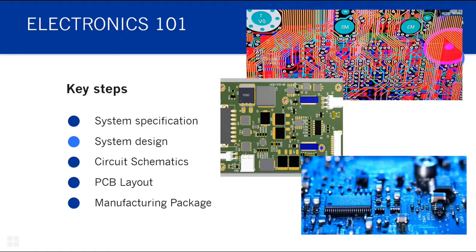Yeah, indeed. The circuit board will typically have a microcontroller on it that hosts the software, and that is what makes the device actually work. So I have been known to make disparaging comments about industrial designers: they design a box and we actually make the thing work. It's a little bit oversimplistic, but to a degree, the role of the electronics and the software in medical devices is hidden, and it can be grossly misunderstood in terms of what significance that is in terms of the overall development cost effort for the device.